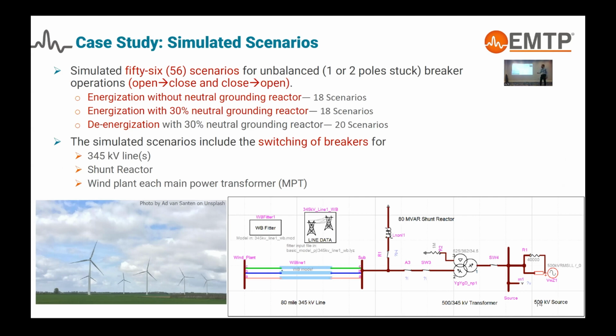And that's why we applied this passive scheme by using a 30% neutral grounding reactor and reran all the cases. We had to rerun all the cases because it is also important to look at whether the addition of this neutral grounding reactor is creating another issue or not. Moreover, we also performed simulation of de-energization, in which we assume that the system is working fine, and then we take out, for example, the MPT and then the line to observe whether there are other issues.